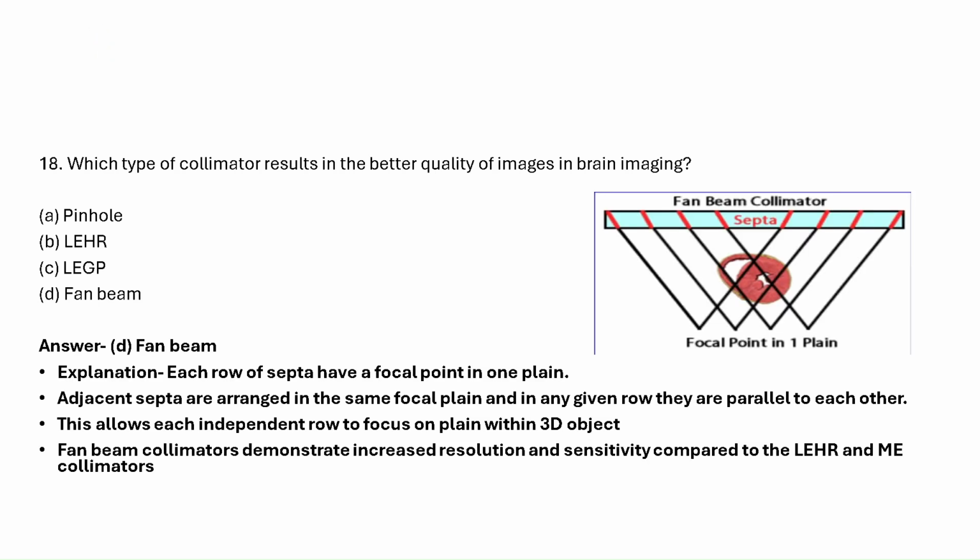Yes, for brain imaging, the fan beam collimator has the best spatial resolution. Basically, the fan beam collimator demonstrates increased resolution and sensitivity compared to LEHR and medium energy collimators, specifically for brain imaging. If in brain imaging you have fan beam as an option, you should always select fan beam as the best collimator, which will result in the best image quality.